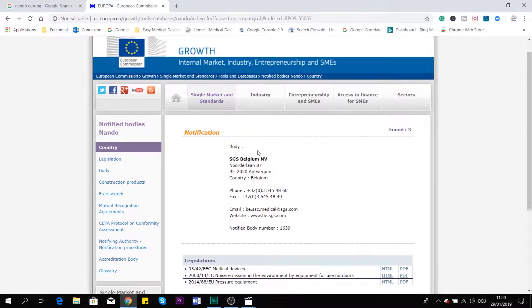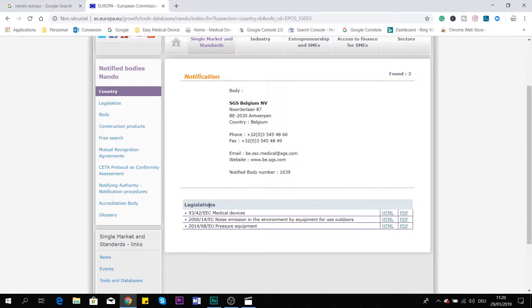This number 1639 is the one that will appear behind the CE mark on the box of your product, if your product is more than Class I — so if it's Class I sterile, Class I measuring function, Class I reusable, or with the new Medical Device Regulation, Class IIa, Class IIb, and Class III. If you want more information about this notified body, you just click on it, and you have all the information. You can see that this notified body is accredited for three pieces of legislation: medical devices, noise emission equipment for use outdoors, and pressure equipment.